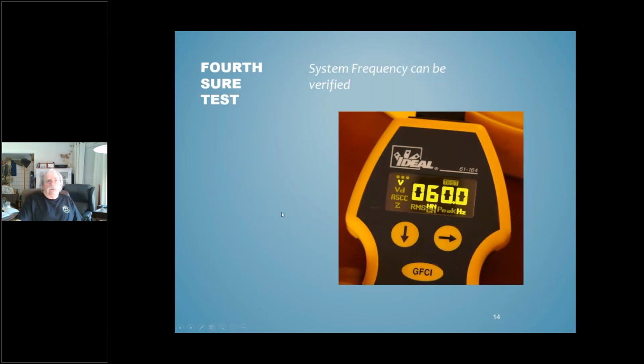Frequency, of course, is important, and this is terrific because if you're installing generators or testing an onboard generator, the frequency and voltage is directly connected to the RPM that generator is running at, and by golly, you can test it right to the point and make sure that everything's as it should be, 60 hertz here in this country.